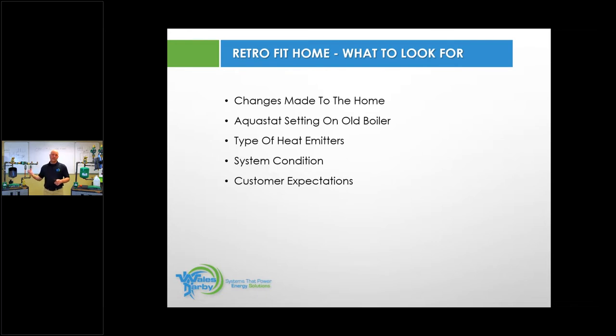I always pull the cover off the aquastat, and I want to know what the operating temperature of that boiler is when it's at max temperature. Usually numbers we always have in our industry are 160, 180. If I go down there and pull the cover off and that's at 200, I've got to find out why that's at 200. I'm probably trying to get more heat out of my heat emitter because I may not have enough, or something is undersized more than likely and they elevated the temperature to offset for undersizing of baseboard. That is key.